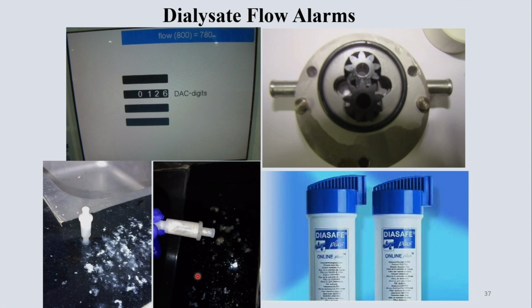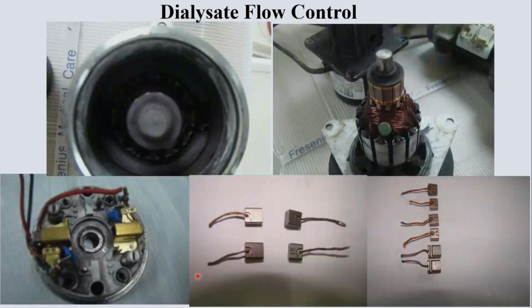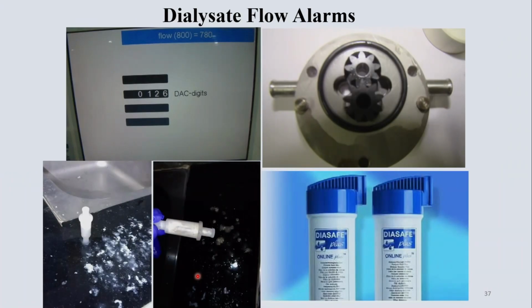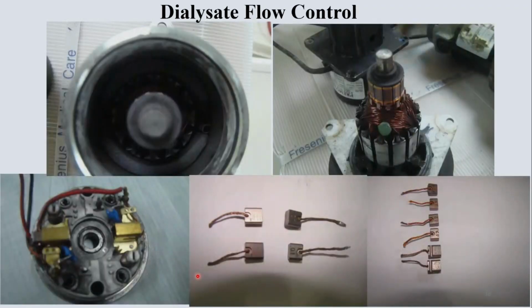Now, when your sieve filters and your degassing filters get partially blocked, the gear head would tend to heat up. What you can see at the previous one, Vipul? Yeah. On the left-hand corner, the technician will increase the digital analog conversion digits, make the motor run faster, and overload the motor over a period of time. Next. And that is what eventually will happen. Here, Fresenius, for some reason, still uses carbon brushed motors.